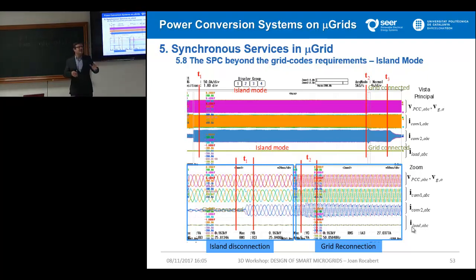Okay? This is very different from the typical converters because when we are making that closing of the main switch, automatically the grid forming should change to grid feeding system. You are going to get a transient when you are not going to exactly control that situation. And you can get unstable conditions. This is not a problem with SPC. Okay? It's not a problem because it's the same control structure. And you are not going to inject extra power to the grid.